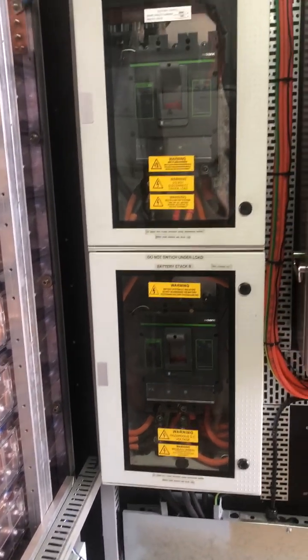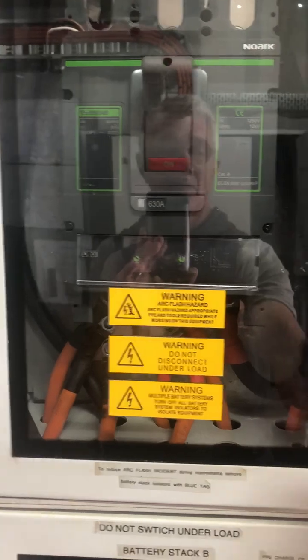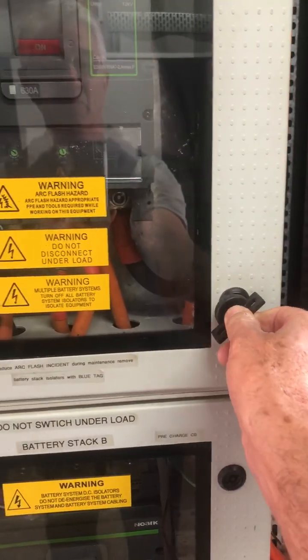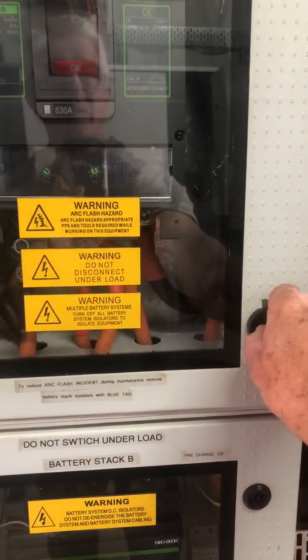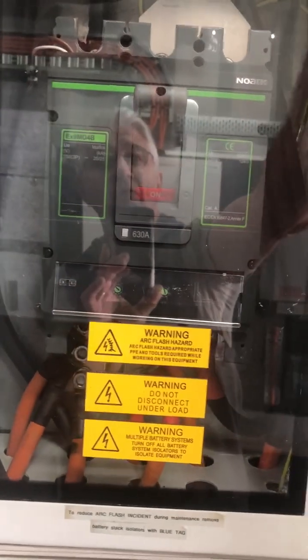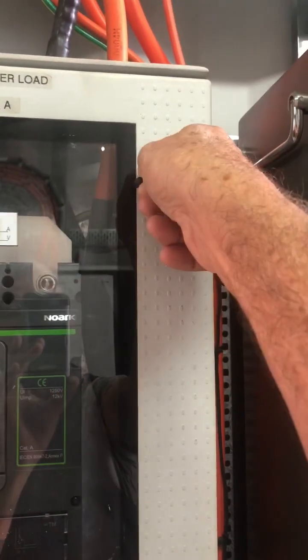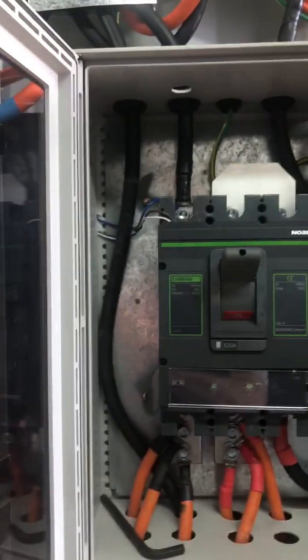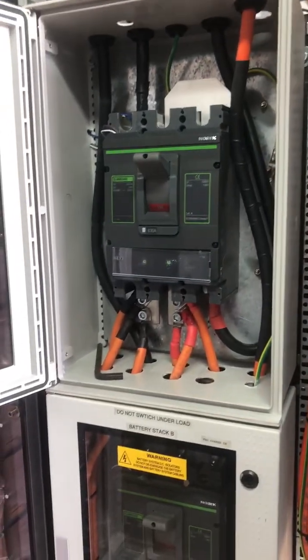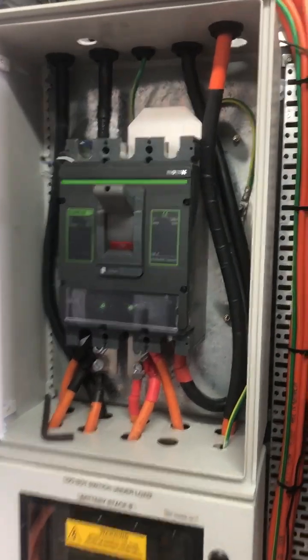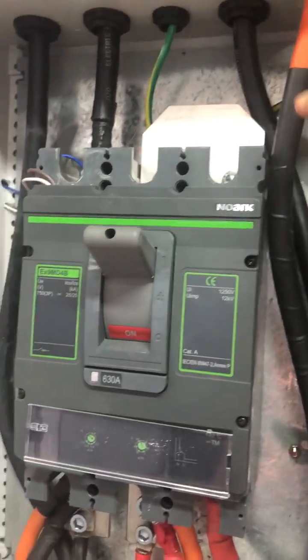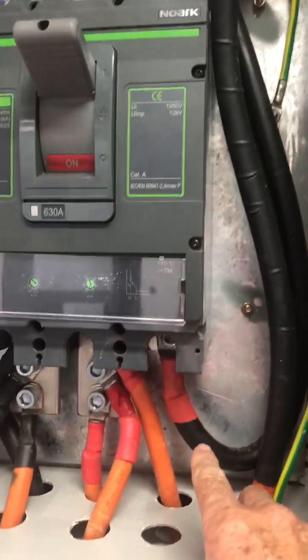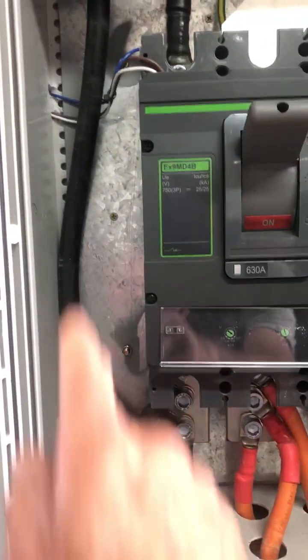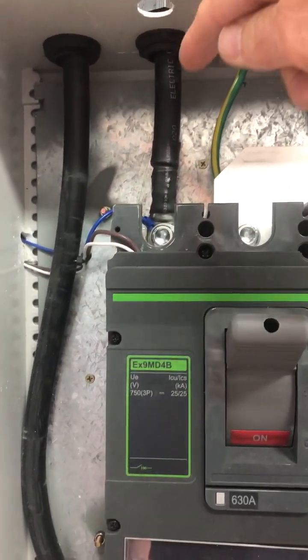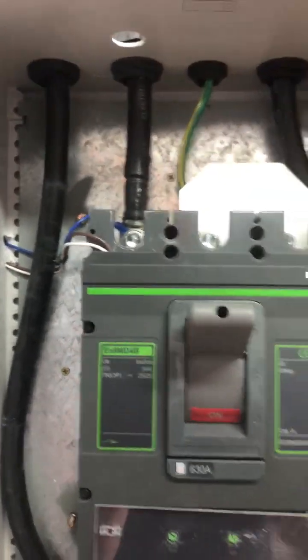And so we have two DC isolators here because, let me just open the box, we have an isolator for each battery string. There's actually two battery strings here. So that's what it looks like on the inside. So this is the active of one battery string, and this is the negative of the same battery string.